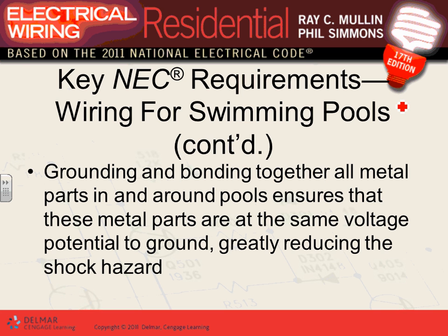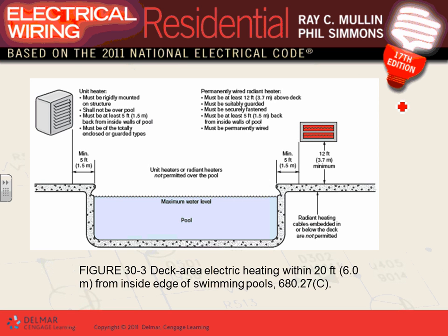So the pipe, the platform that you sit on to jump, the ladder that you use to go down into the swimming pool, all these are bonded with number 8 conductor, number 8 copper. And that's bonding. I'll show you how you do it. By bonding it, they minimize the likelihood that the ladder of the swimming pool will be energized with 120, and the swimming pool platform that you sit on is sitting at 0, and you are grabbing both of them, and you have a perfect shock. So everything is bonded together.